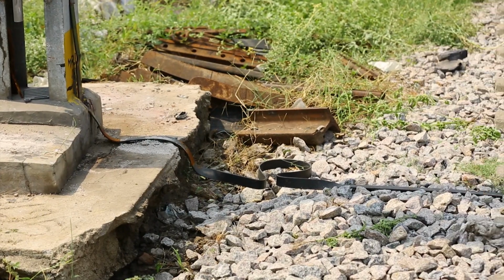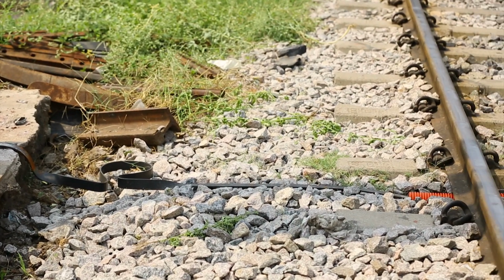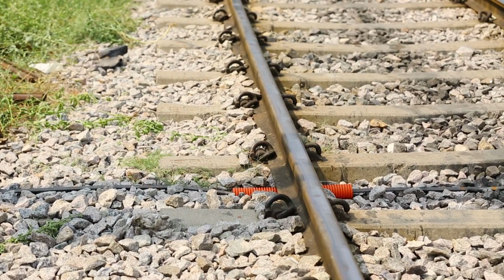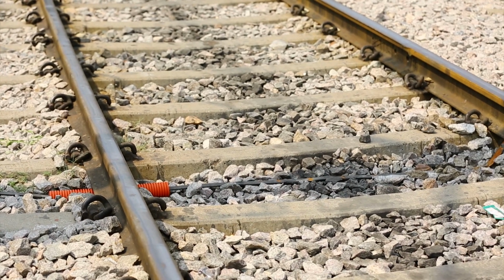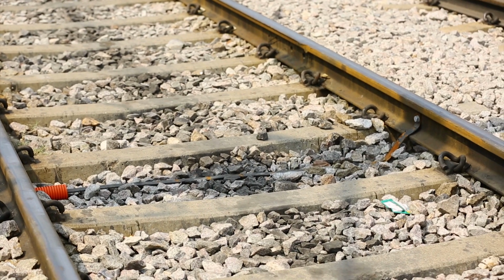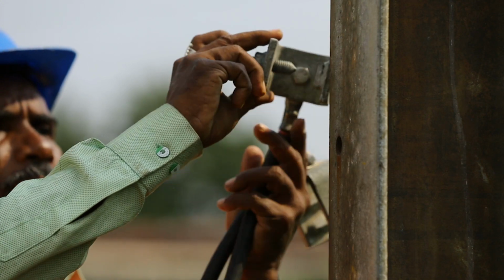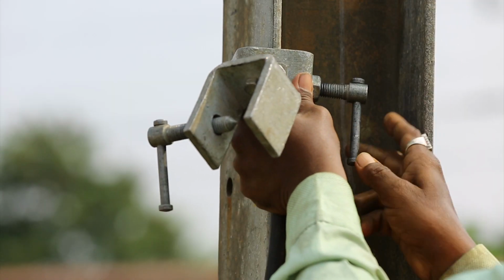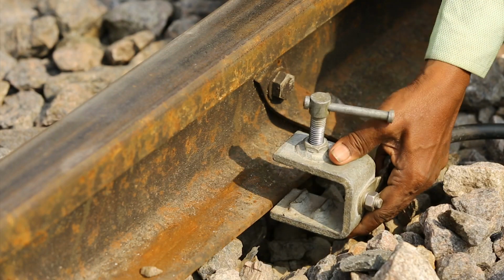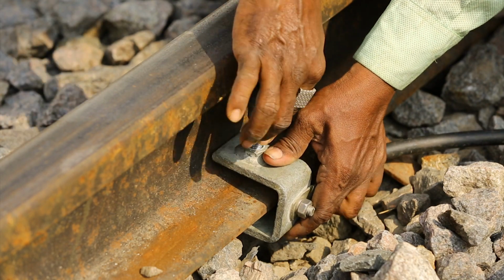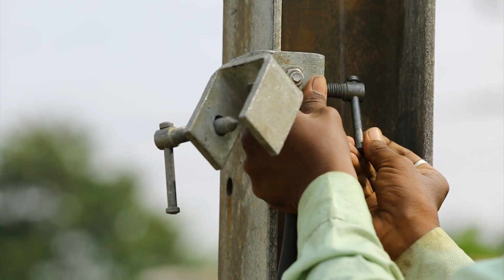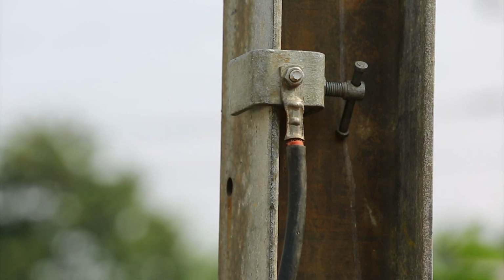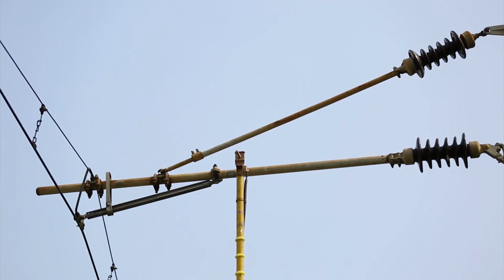For providing earth on the OHE, verify that the mast to which the earth rod is to be fixed has a structure bond and check the healthiness of the bond. Fix the earthing clamp securely to a mast at least one span away. Earthing clamps should always be fixed to the traction rail or mast first. Then the top clamp must be tested on RT or BT and hooked to the contact wire.